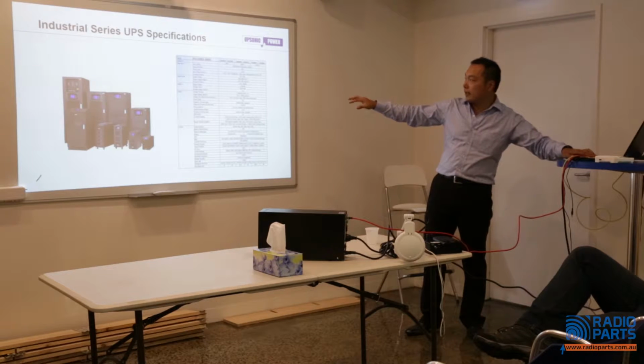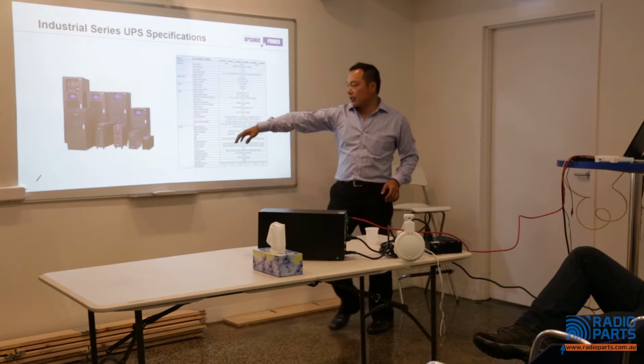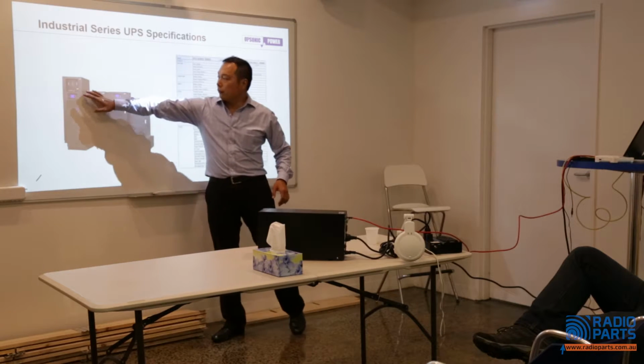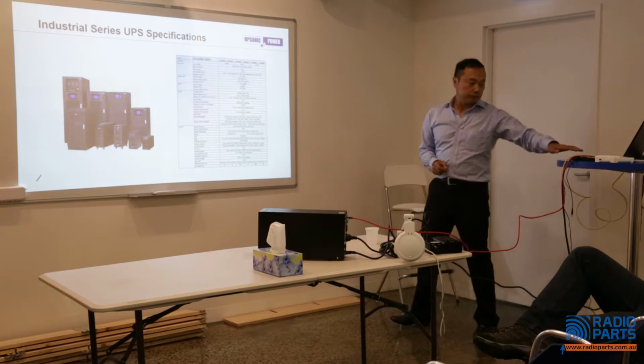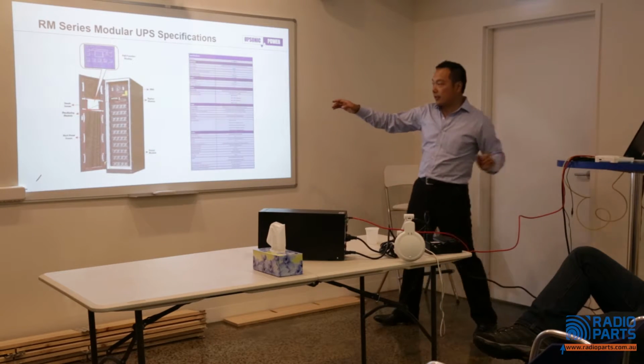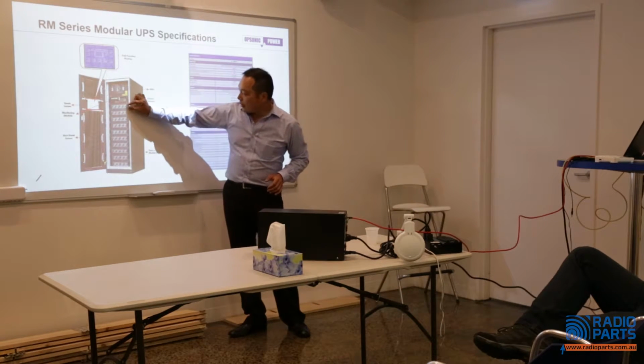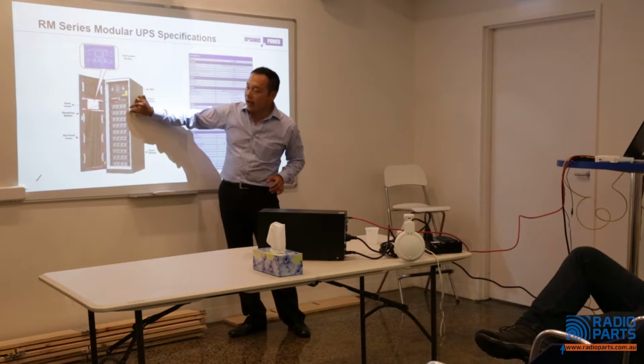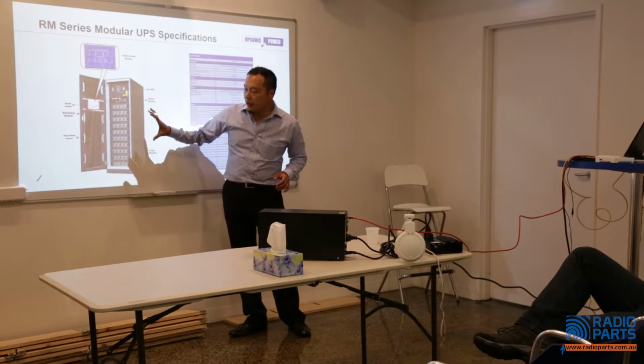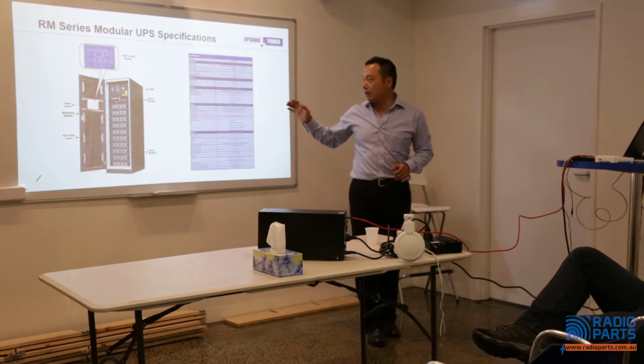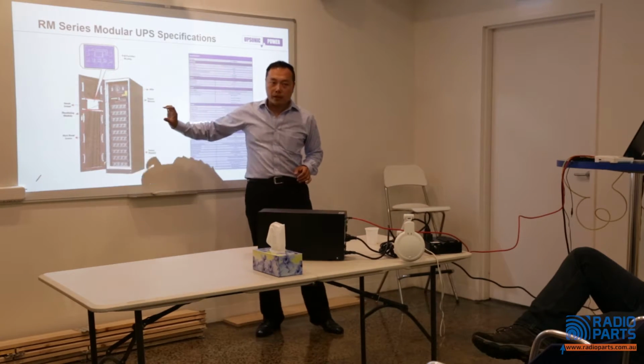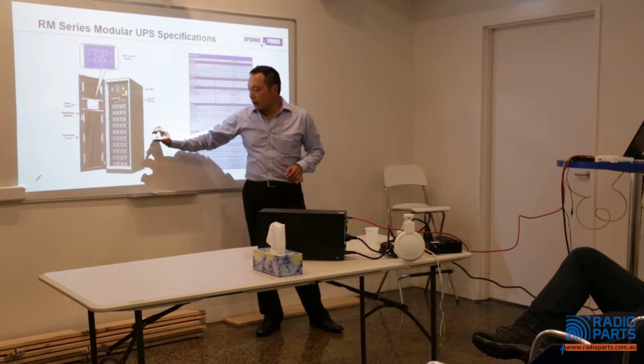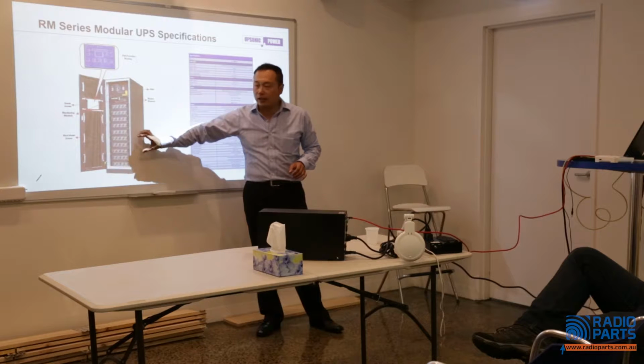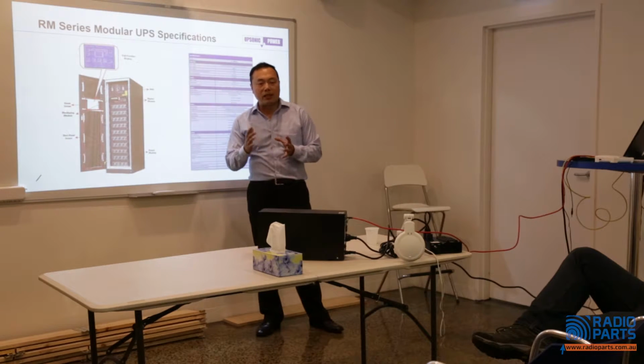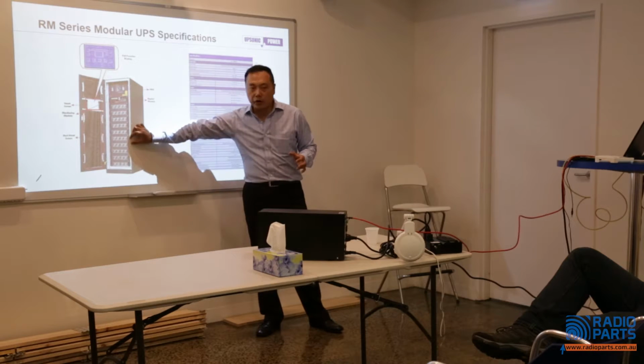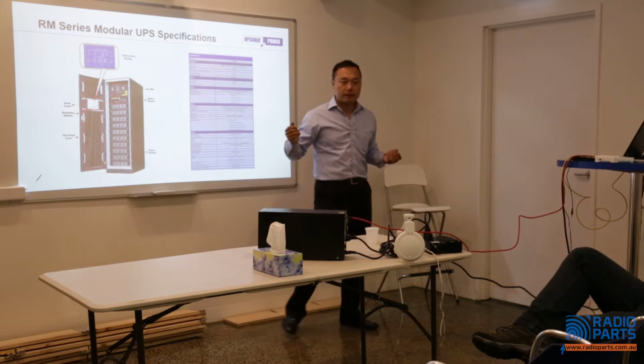Here's the industry UPS, big capacity from 6 kVA to 200 kVA. This is a modular UPS, so there is a power module. Each module is 20 kVA. Up to 10 modules can be inserted to get a 200 kVA UPS, and it's hot swappable. So initially, if you need, you can just buy 2 or 3 modules, that's 60 kVA. And then if your business expands in the future, just buy more modules and plug in. That's it.